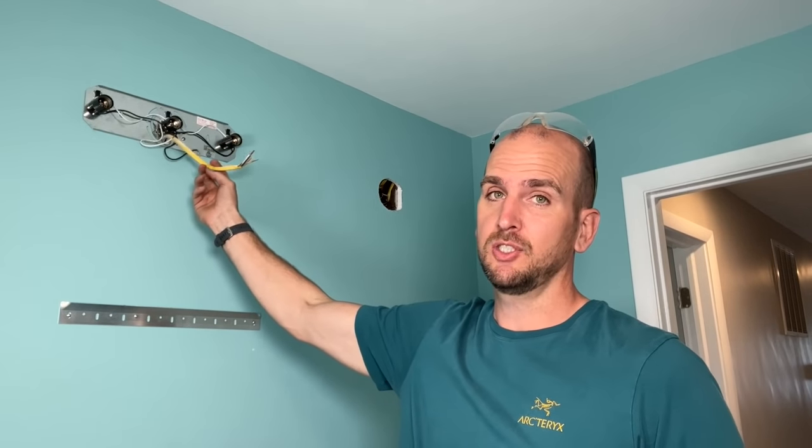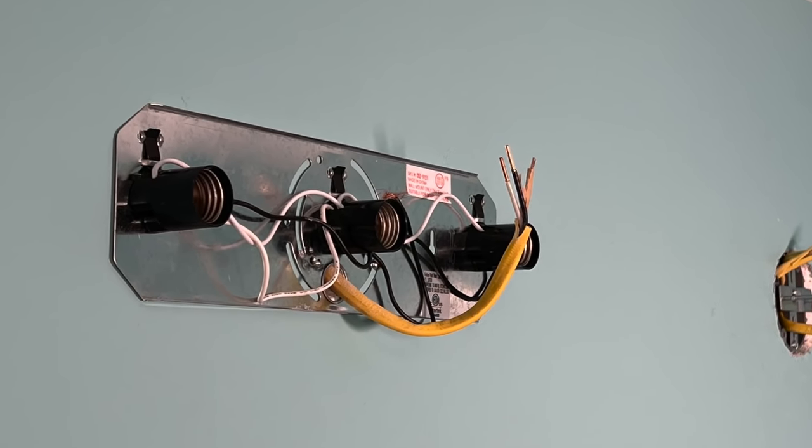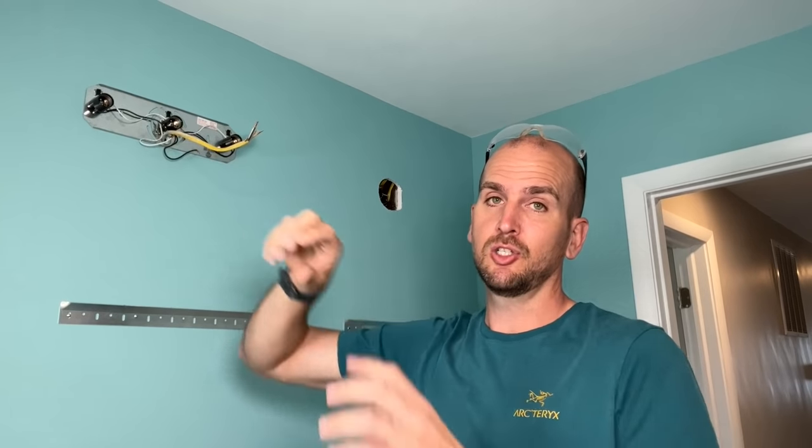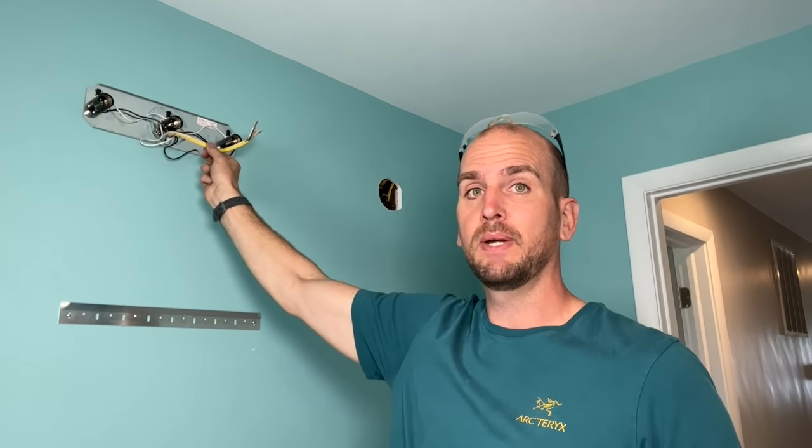So one of the most common ways to not install a vanity light and issues that don't meet code is a scenario such as this. You have a very cheap vanity light that has these mounting plates and because you have the mounting plates you can kind of just screw it into the drywall, drywall anchors, or maybe actually hit a stud to mount it and then your Romex just comes out and into the small plate area between your outside trim piece and your plate. Now that's not correct and this would increase the likelihood of this Romex or this non-metallic sheathing and the insulation around the wires to get damaged and possibly cause an issue like a short later on. So don't do that and if you have that at your house might be something you want to fix sooner rather than later.